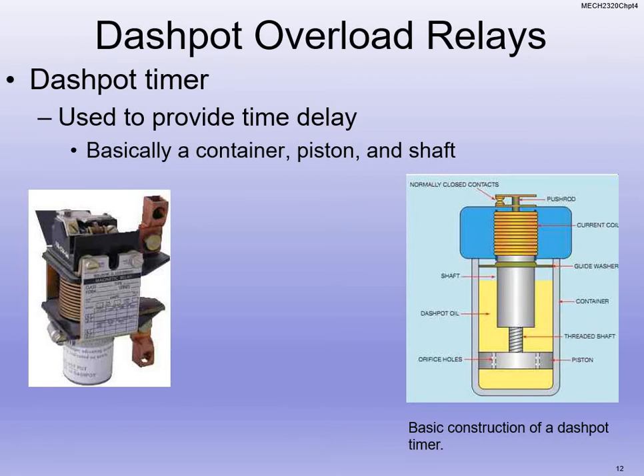So that magnetic field, that plunger still has to overcome the fluid of the oil. Based on that, if the current rushes in, it's going to move that piston enough to where it'll start to pull it up. But if it levels back out, that piston will stay in place, and we'll have our contactors closed. But if that inrush current is too long, based on whatever the time delay is on the oil and the piston and all the other properties that go into it, it will open the contactors and protect it.